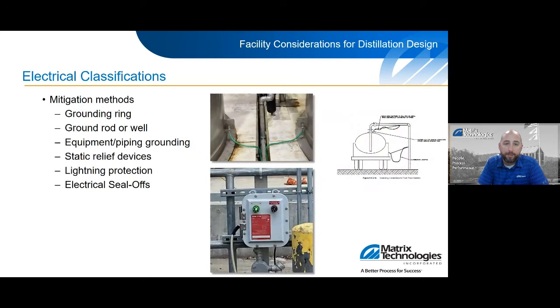Just a few mitigation methods for the electrical classifications for the space. You've got grounding rings, rods, or wells. These could be existing or new. It's important that you make sure that your facility has some sort of ground on site, so that way you could properly discharge any static that might exist. You've got equipment and piping grounding. This is tanks, columns, mezzanines, and even bonding between pipes. The top left picture there kind of shows the bonding of the tanks to the steel that was underneath it. So during your tank design, it's important that you incorporate these tabs or some sort of mechanism to attach that grounding to. We've got static relief devices.